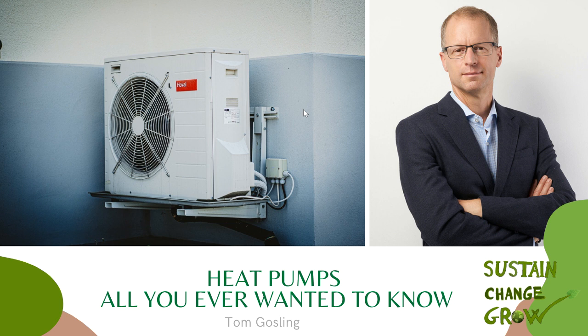But heat pumps work even in homes that aren't that well insulated. I think the point is that you want to be operating your heat pump at the lowest possible temperature because then it's as efficient as it can possibly be, and then it's going to be as cheap as it can possibly be. And what determines the temperature that you need to operate your heat pump is the heat loss from your home. So the more heat you have leaking out of your home, the higher the water temperature you need in your radiators to compensate for that heat loss.